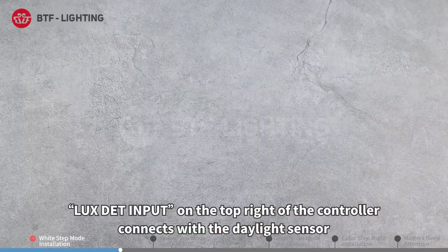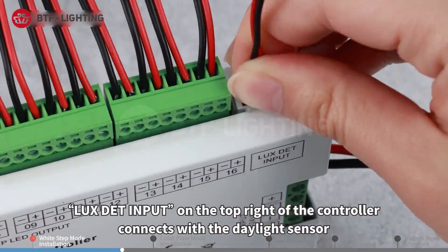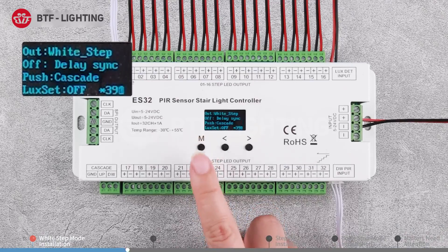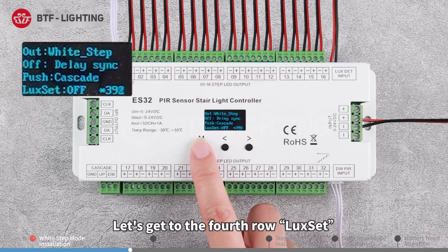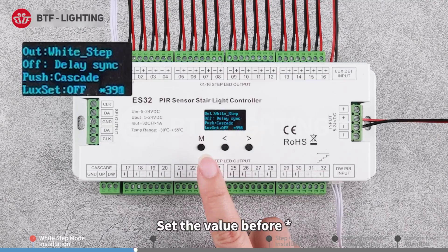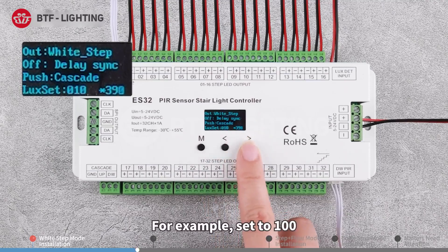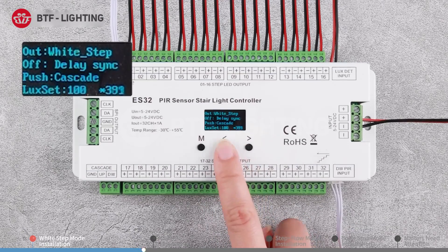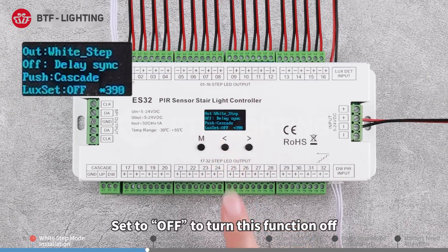The LUX DET input on the top right of the controller connects to the daylight sensor. Long press the M key for two seconds to access the settings. The number following the asterisk is the current ambient brightness value detected by the sensor. Set the value before the asterisk — for example, set to 100 — so that when the detected ambient brightness exceeds 100, the lights won't turn on. Set to OFF to disable this function.